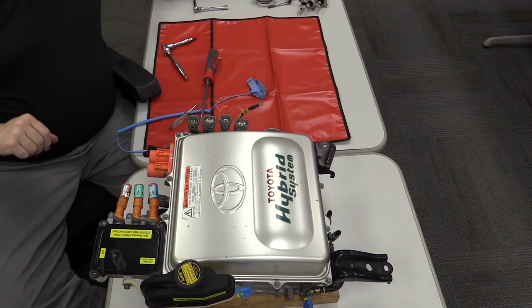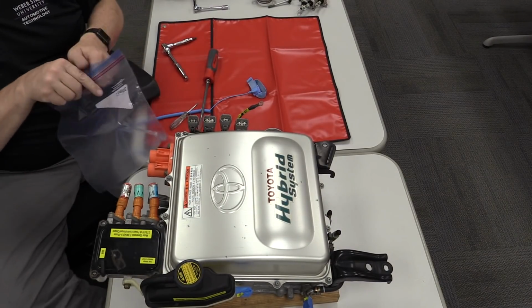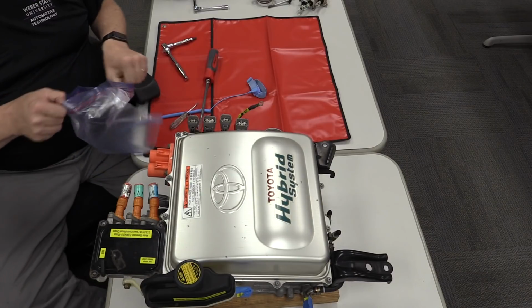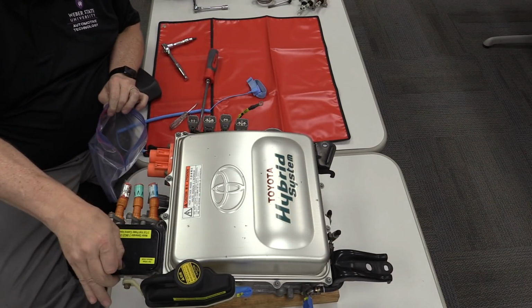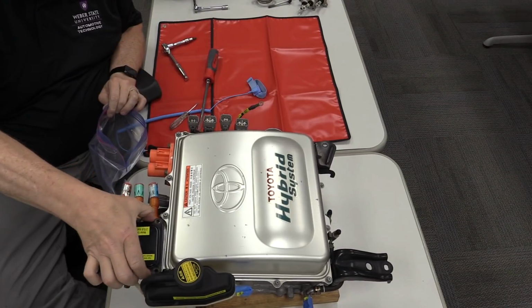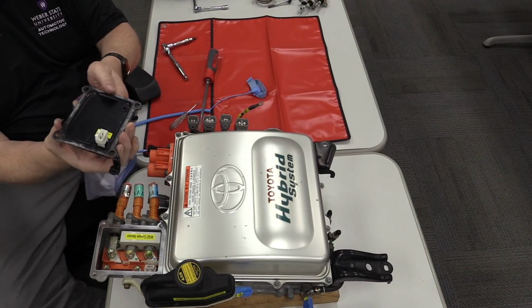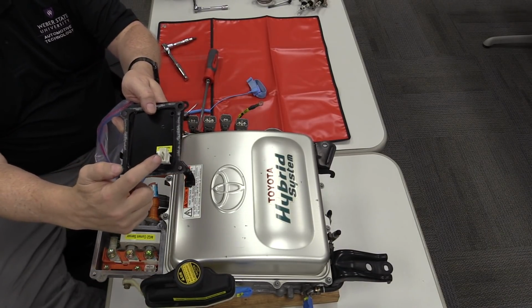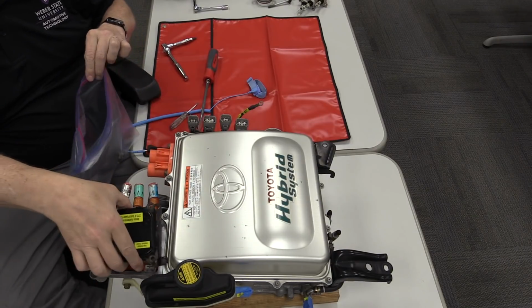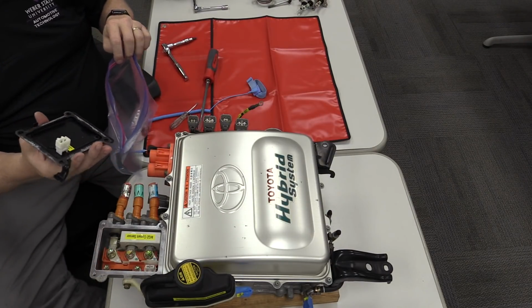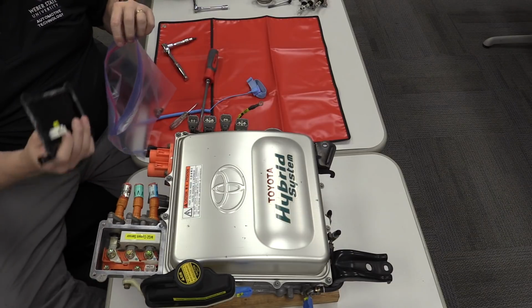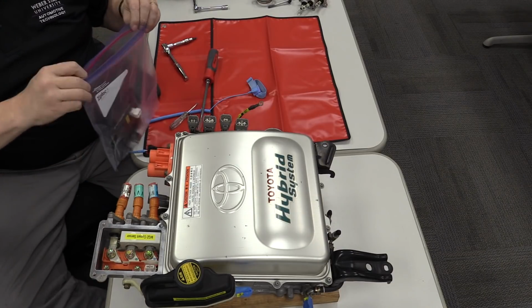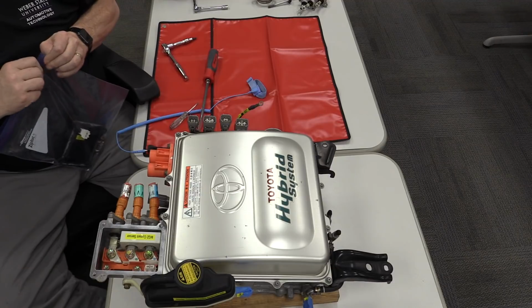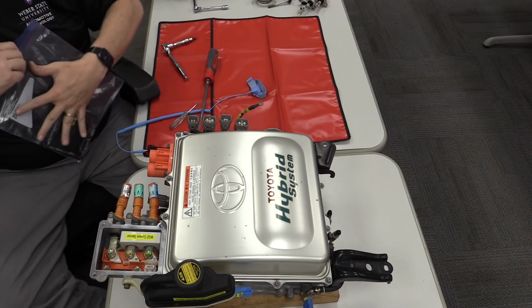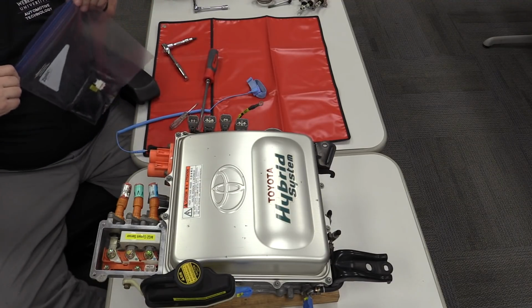So we get those four bolts out and lift up the cover. This cover, as we lift it up, also has a high voltage interlock circuit on it. So if somebody took this off and didn't know what they were doing, weren't properly trained, it should open circuit the contactors we talked about and disconnect the DC power from the inverter converter assembly.